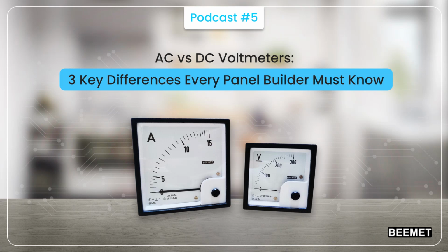The second difference is related to how these voltmeters are applied inside electrical panels. DC voltmeters are typically used in control sections, battery banks, and UPS systems where voltage remains stable. In contrast, AC voltmeters are used in supply lines, transformer outputs, and distribution sections where voltage is alternating. Modern panels often use digital voltmeters, including multifunction devices. However, it is important that the configuration of the meter matches the type of waveform being measured.